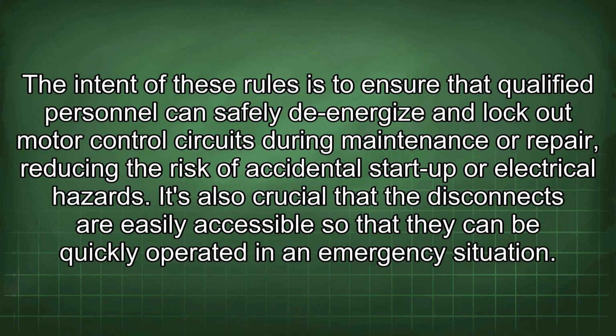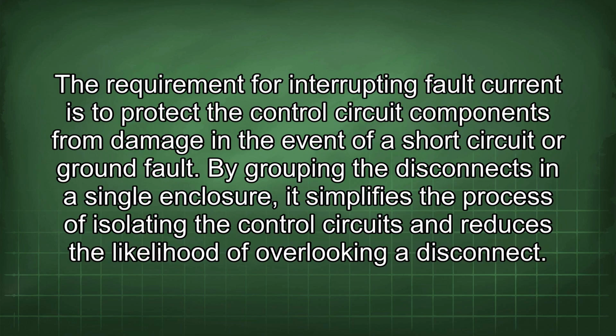The intent of these rules is to ensure that qualified personnel can safely de-energize and lock out motor control circuits during maintenance or repair, reducing the risk of accidental start-up or electrical hazards. It's also crucial that the disconnects are easily accessible so that they can be quickly operated in an emergency situation. The requirement for interrupting fault current is to protect the control circuit components from damage in the event of a short circuit or ground fault.